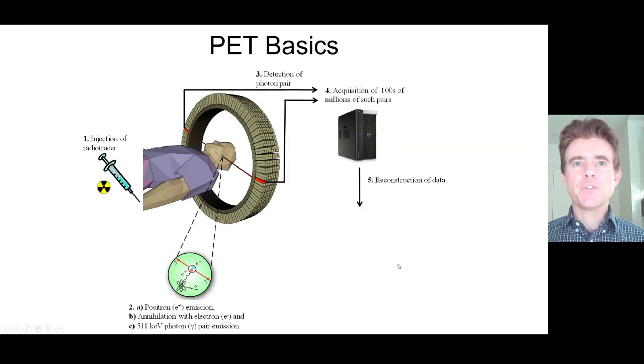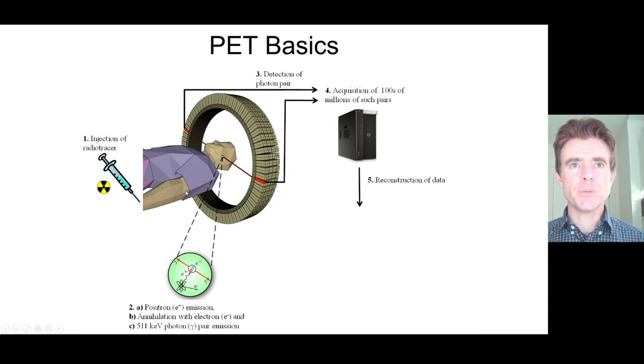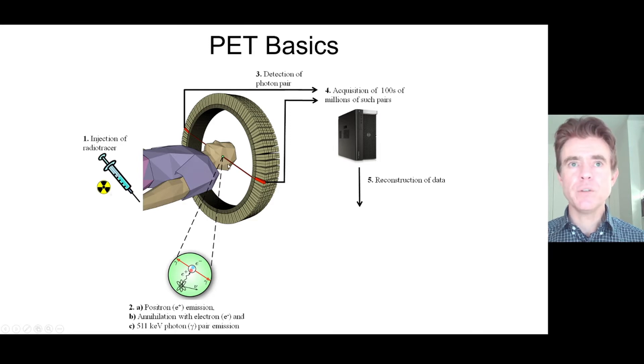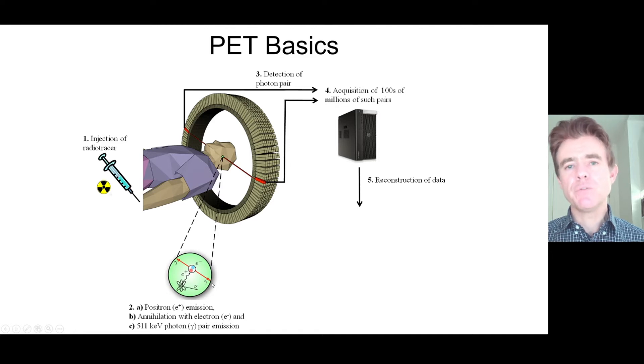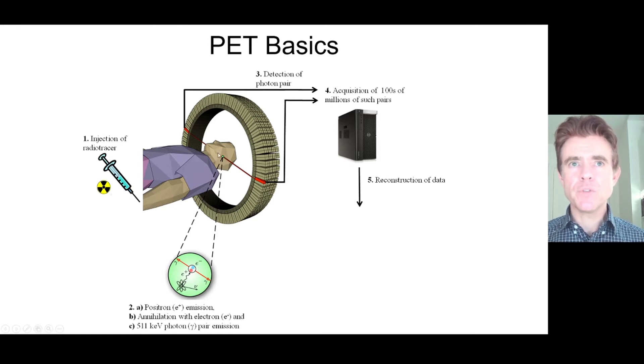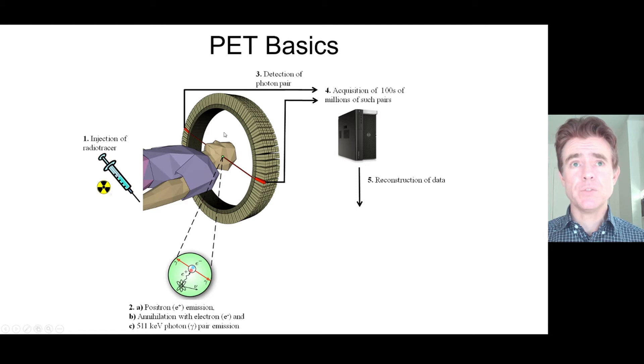The very basics of PET involve administration of a radiotracer to the bloodstream of a patient or subject under study. This gets taken up in various tissues, including the brain. Because this radiotracer is a positron-emitting compound, the positrons emitted will annihilate with electrons, and we get back-to-back high-energy photon pairs, each of 511 keV. These are energetic enough to escape from the brain and be detected in the ring of detectors that constitutes the PET scanner — high-density crystals designed to stop high-energy photons.